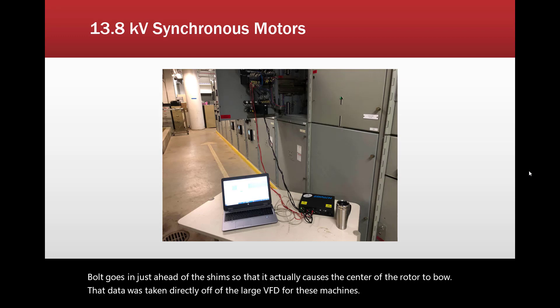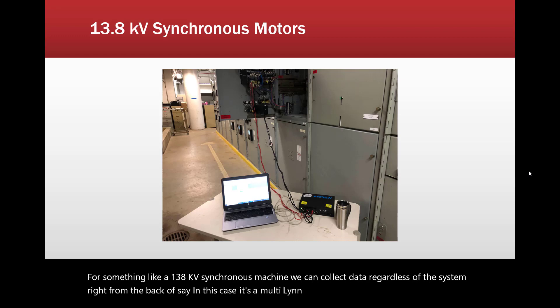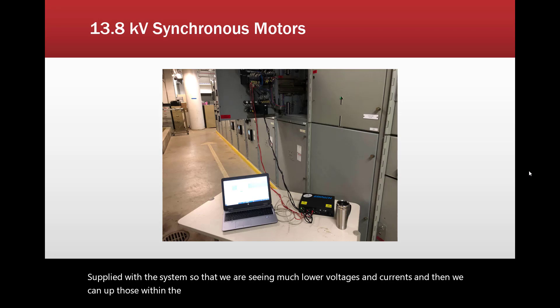For something like a 13.8 kV synchronous machine, we can collect data regardless of the system, right from the back of — in this case a Multilin — collecting data right off the CTs and PTs supplied with the system so that we are seeing much lower voltages and currents. We can then scale those up within the software so that we're seeing the actual values.